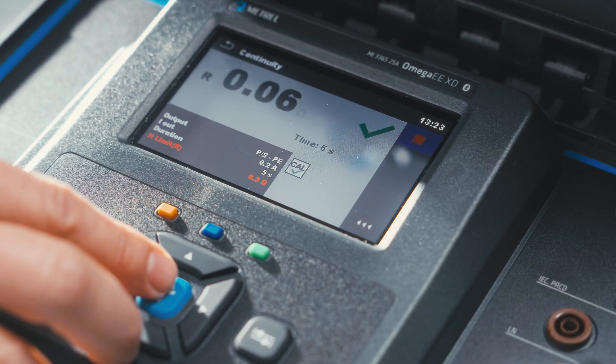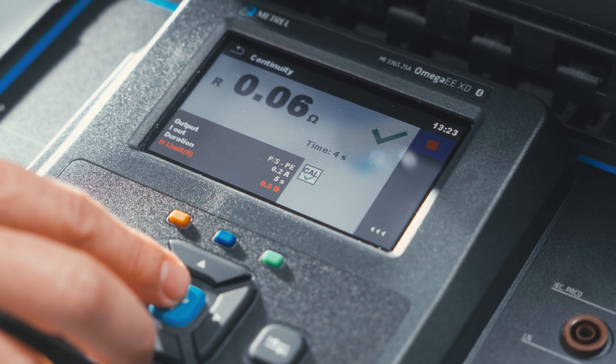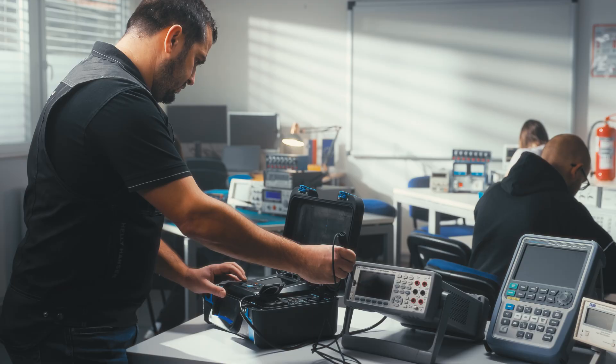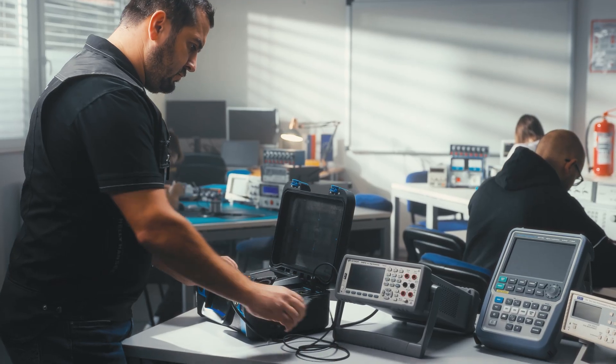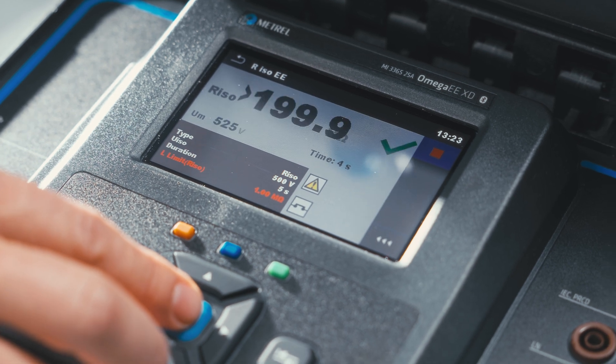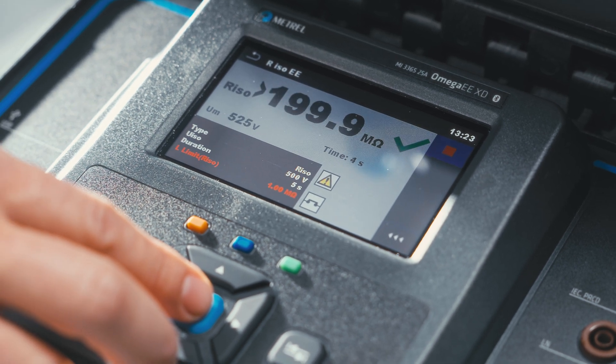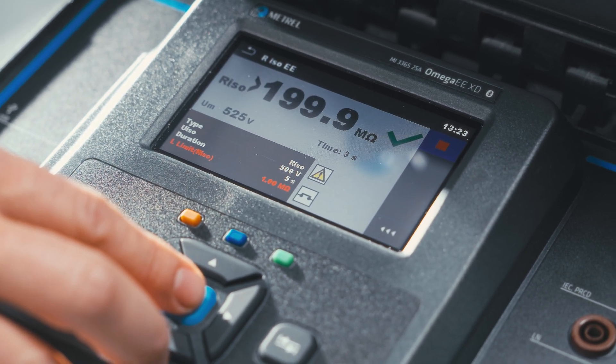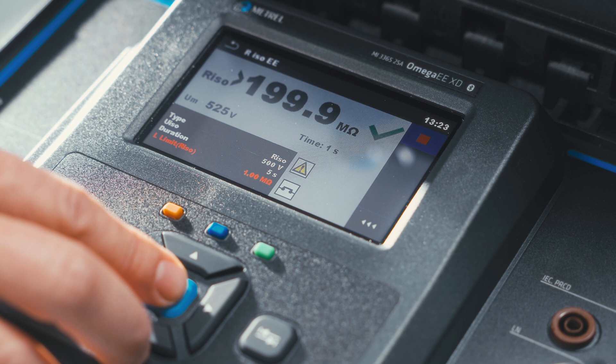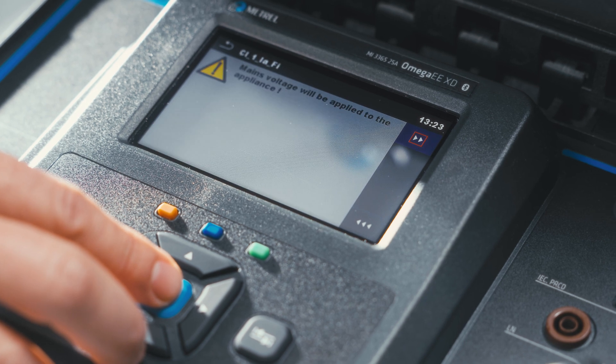Continuity of the protective conductor comes first, followed by the measurement of insulation resistance of the protective conductor to the neutral and phase conductors.